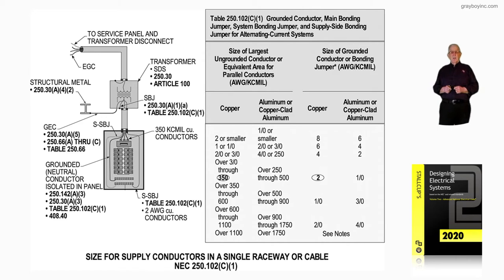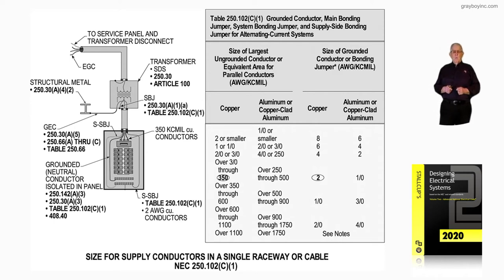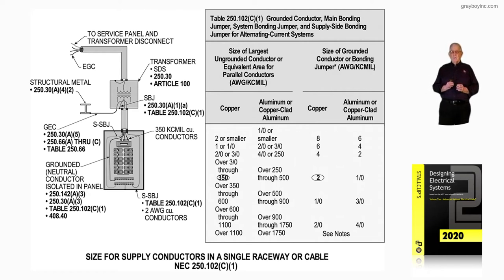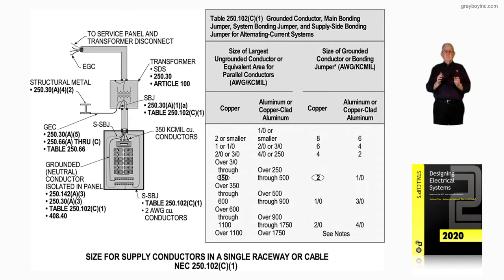This illustration deals with sizing supply-side conductors in a single raceway or cable in accordance with 250.102C1. Before we get into the illustration, notice this table is highlighted — Table 250.102C1. If we review the very top portion of the table, it talks about the grounded conductor, main bonding jumper, system bonding jumper, and supply-side bonding jumper for AC current systems. This information tells you exactly how to use this table to size those items.